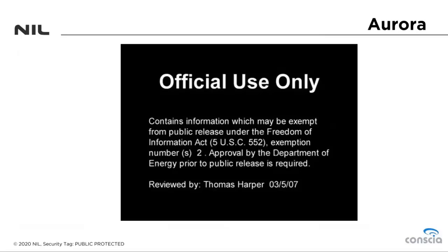In the experiment, the researchers assumed that an attacker somehow gained access to protective relays. Protective relays are designed to continuously monitor for dangerous conditions. If the dangerous conditions are met, protective relays open circuit breakers and disconnect the electrical source from the electrical grid. In our case, this would be the diesel generator.